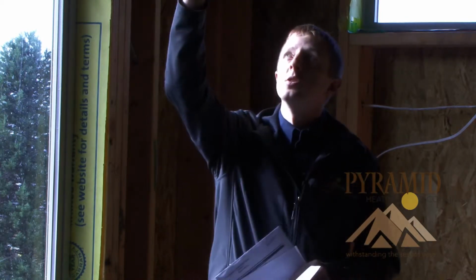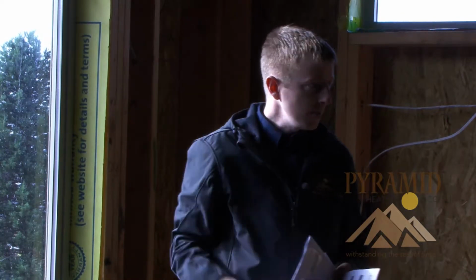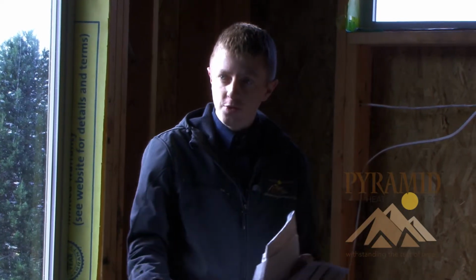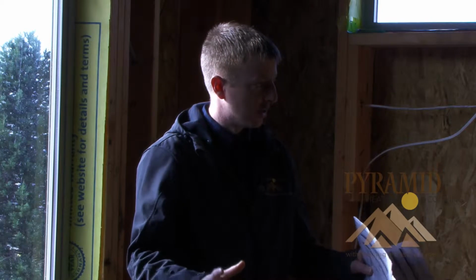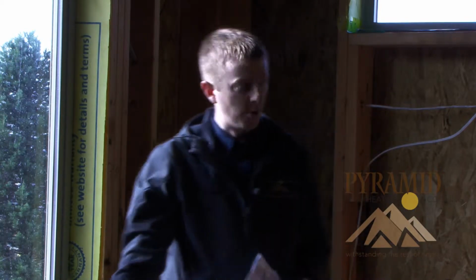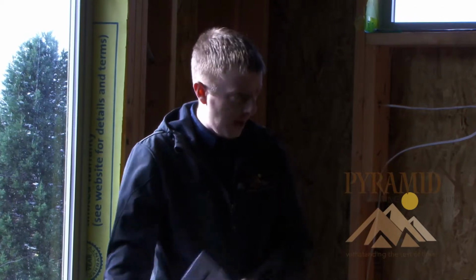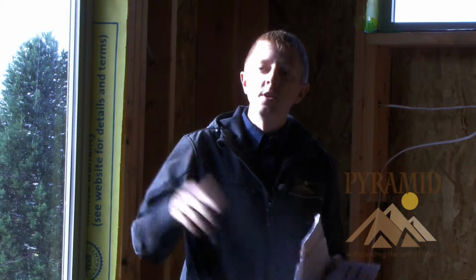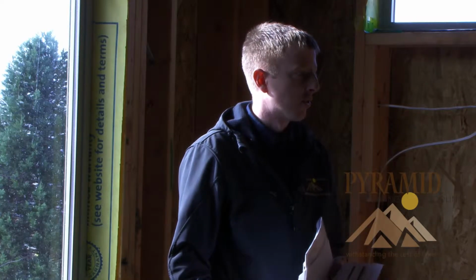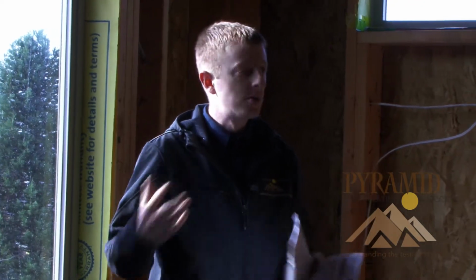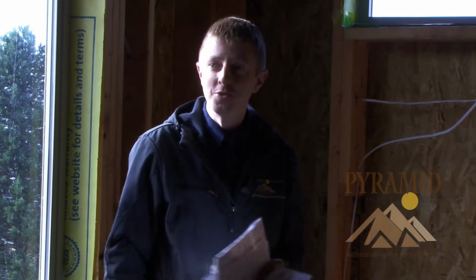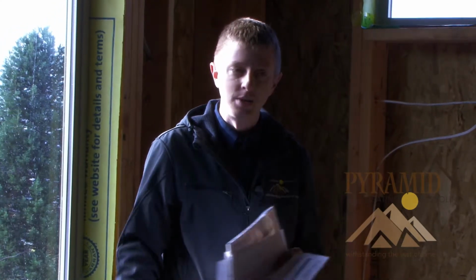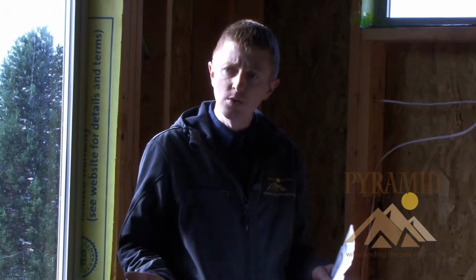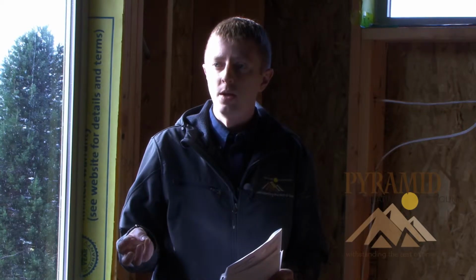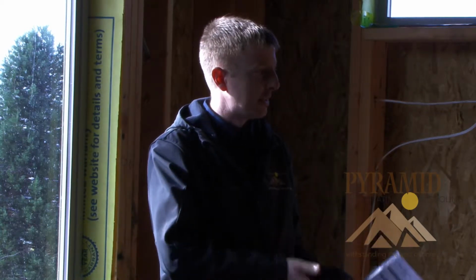The big difference too is we see their ceiling registers on the main level. With the square footage we have here, furniture location matters: if you put a couch here and the register is underneath the couch, you've just eliminated the conditioning ability for that register in this room. In the ceiling, you can put furniture wherever you want, much more flexible. Upstairs, they're in the floor, much different than you folks who have the heating systems up in the attic through the ceiling. They're in the floor, strategically located, so near areas where furniture isn't typically placed.